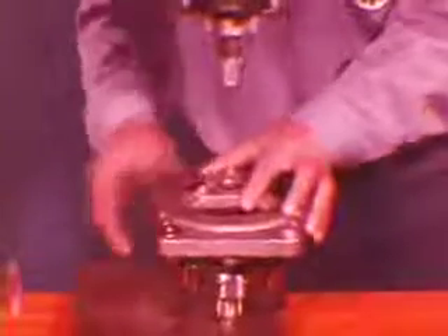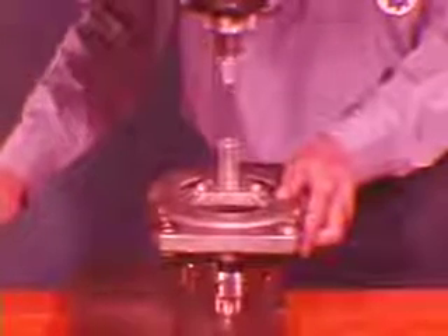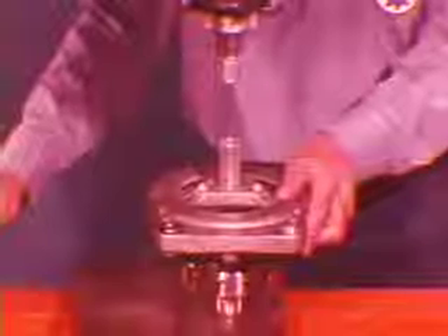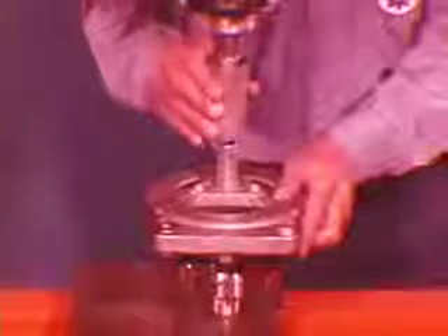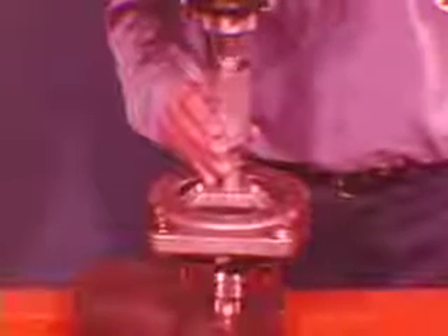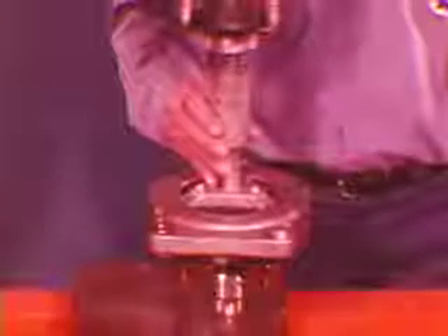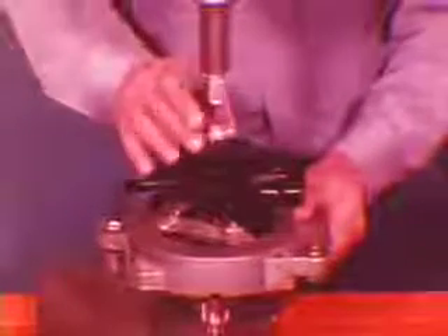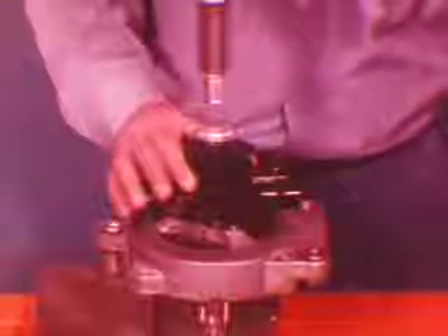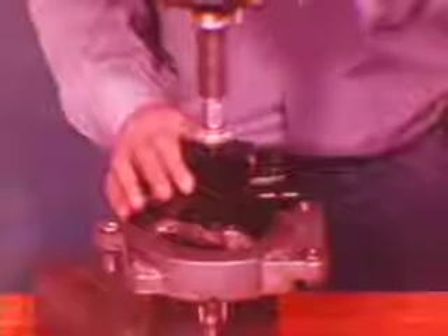To install the drive end bearing, first seat the bearing in the end shield and install the bearing retainer parts. Support the slip ring end of the rotor shaft on the press bed. With the bearing spacer installed, position the shield and bearing assembly squarely on the drive end of the shaft. Then hold the installing tool in place on the bearing hub and press the assembly onto the shaft until the hub contacts the spacer. Remove the installing tool and start the pulley on the shaft. Again, support the slip ring end of the rotor shaft to protect the bearing and press the pulley on until it contacts the drive bearing hub.